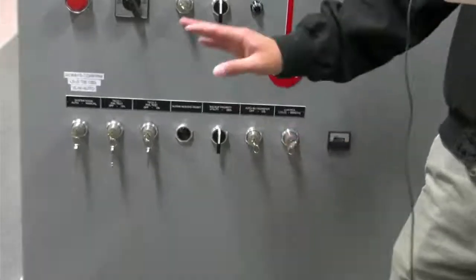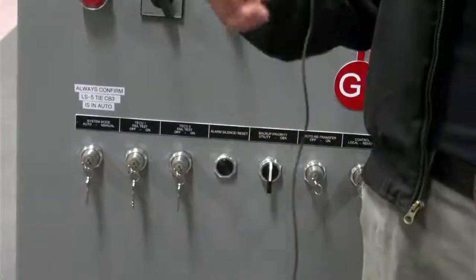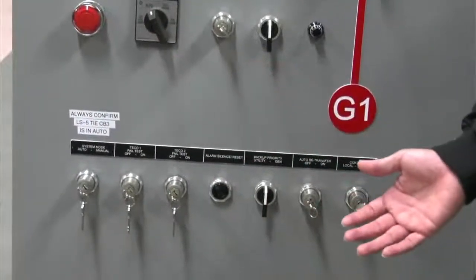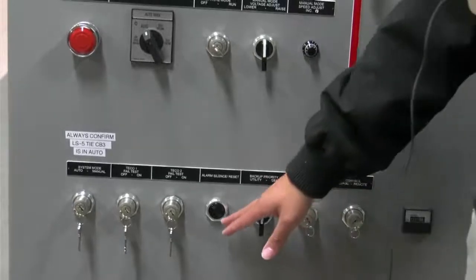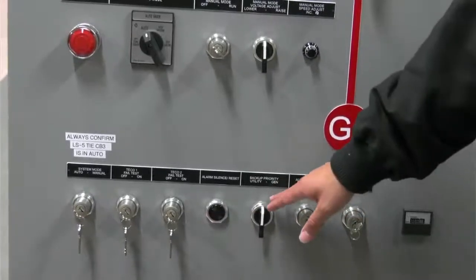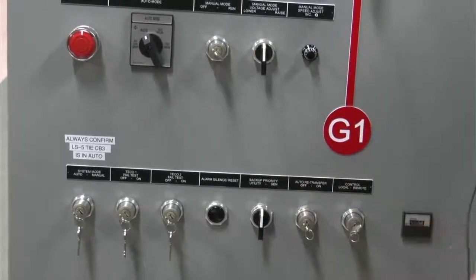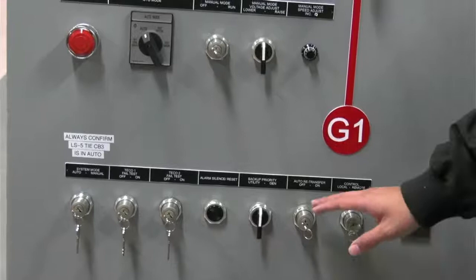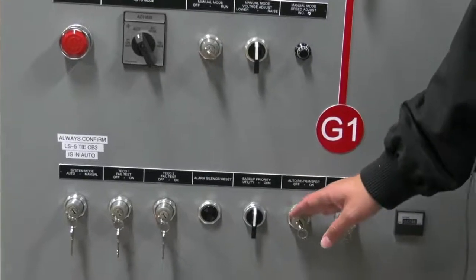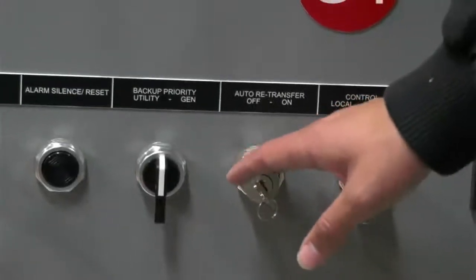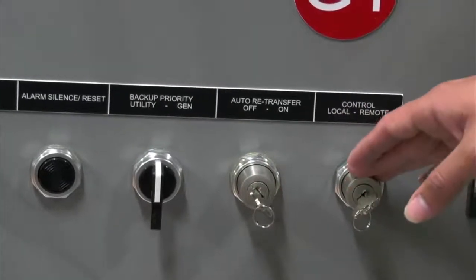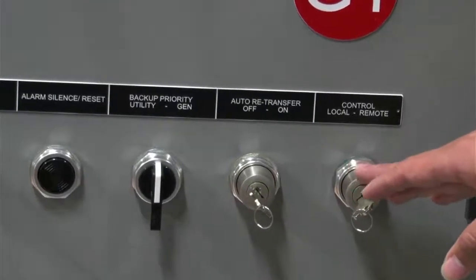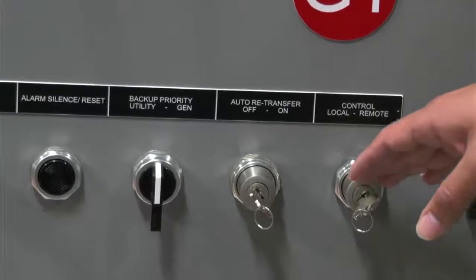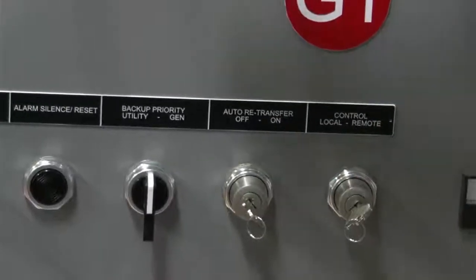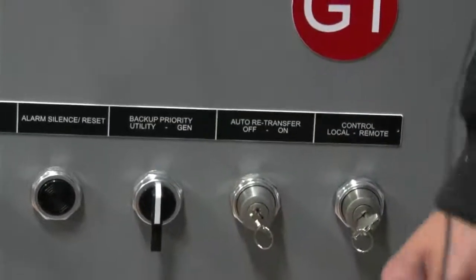On the bottom right, we have the main switches where we can set the system to work on manual or auto. We can simulate some failures. We can reset alarms. We can change priorities. I'm going to explain this a little later. We have the option to retransfer, which I'll also explain later. And also to set the control to local or remote. This basically gives you the option to control the system using these switches or using the DCS via Modbus.